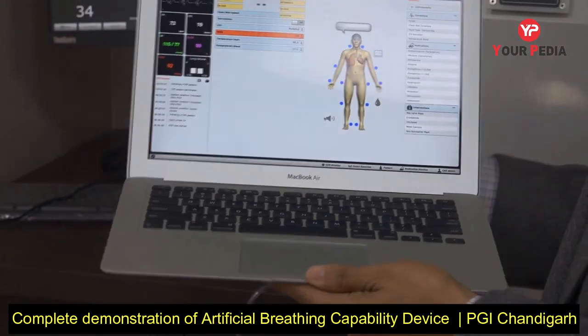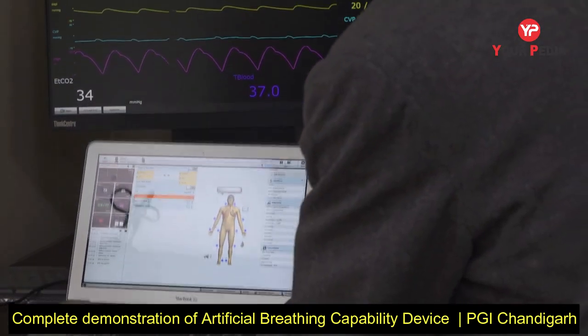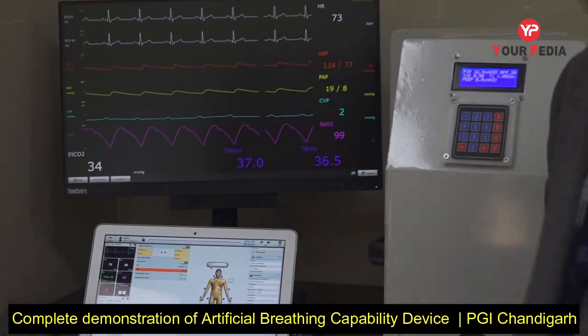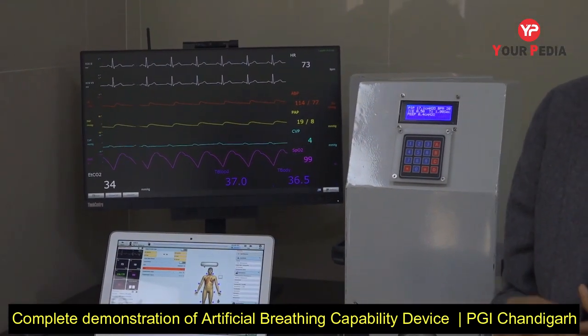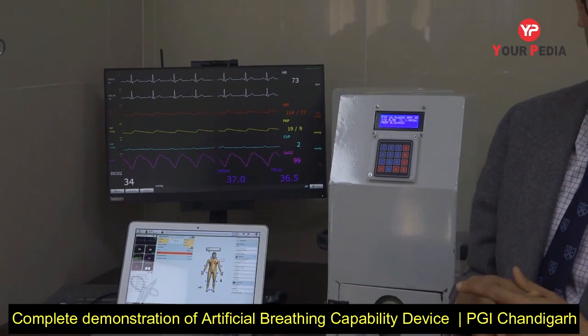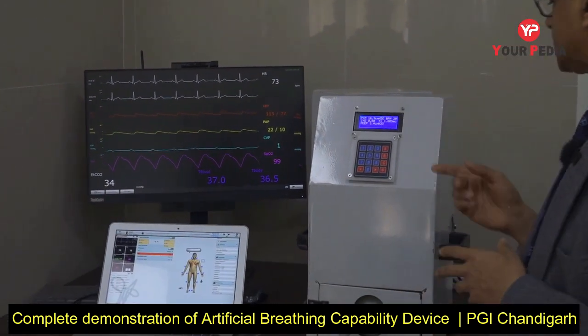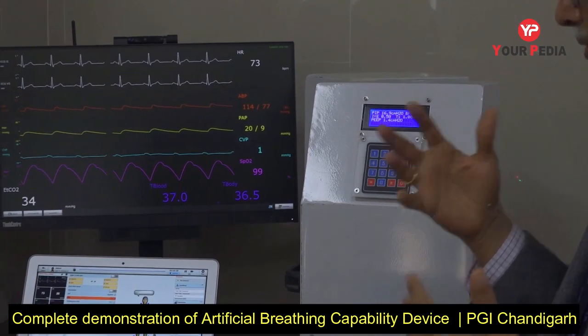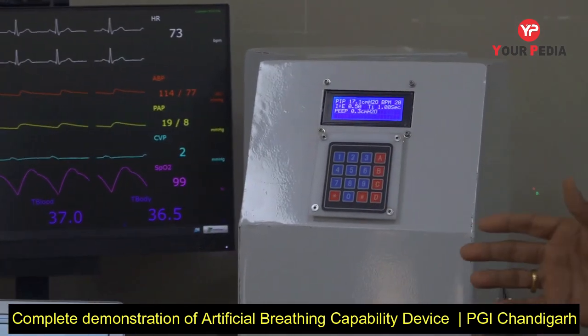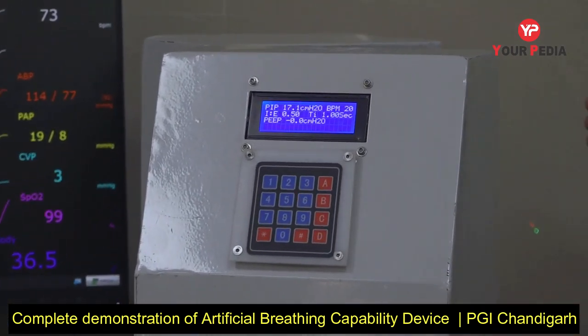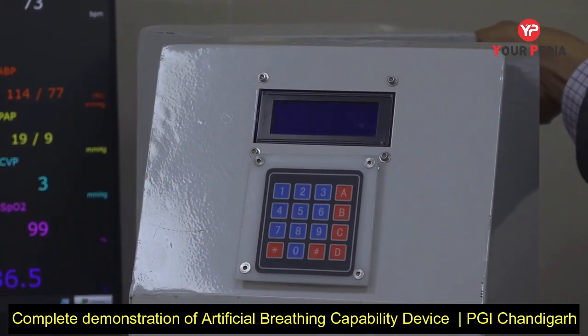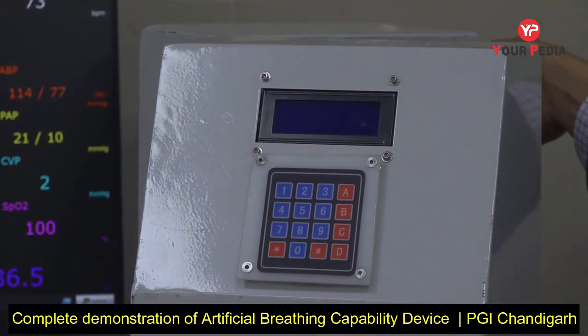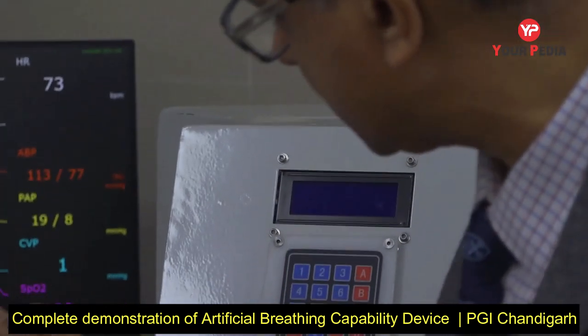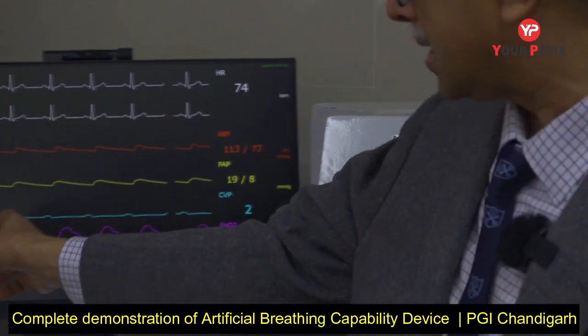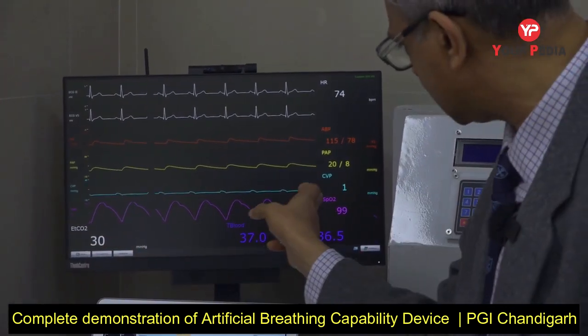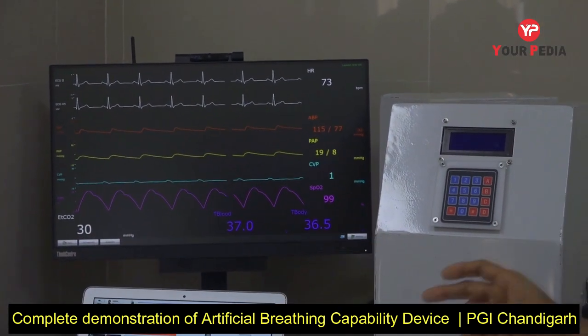Now this is what a patient would look like in an adult who's having a respiratory failure but with relatively normal lungs, in the sense that he has not very high pressure requirements. We could also reset this particular device to go for higher ventilation parameters, and I will show you that also in a moment. So we'll switch off this device briefly for a minute, and as we switch off the device, you'll find that there is no ventilation going in. So the end tidal CO2 starts to drop down. The saturations will take a little while to drop down as well.